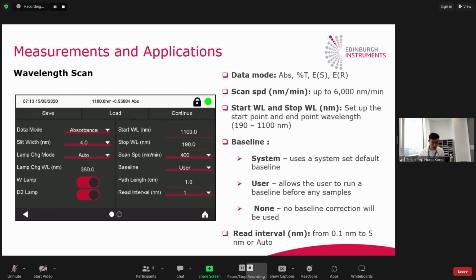For the wavelength scan, when you select it, you will enter the parameter pages. Here for the data mode, you can select the absorbance, the transmittance, the energy on the sample, and the energy on the reference. The maximum scan speed is up to 6,000 nanometers per minute. Then you can set your starting wavelength and also the stop wavelength, from 190 nanometers to 1,100 nanometers.